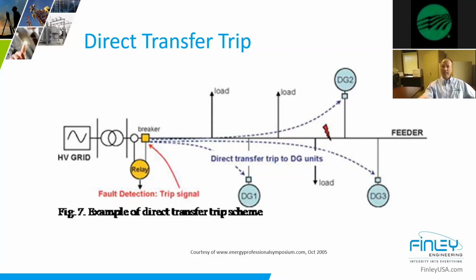But even on those kinds of feeds, when sub-devices talk to and coordinate with downstream devices, especially with the impact of DG being mid-feeder, you've got the potential for these devices to talk, coordinate, and eliminate the potential for nuisance trip—one device saying, no, I'm taking this fault, you're not—so you can segment and coordinate. But until you have smart grid adoption with better devices that can do those things, and communication means that allow that distribution automation potential, you don't have a way to mitigate.